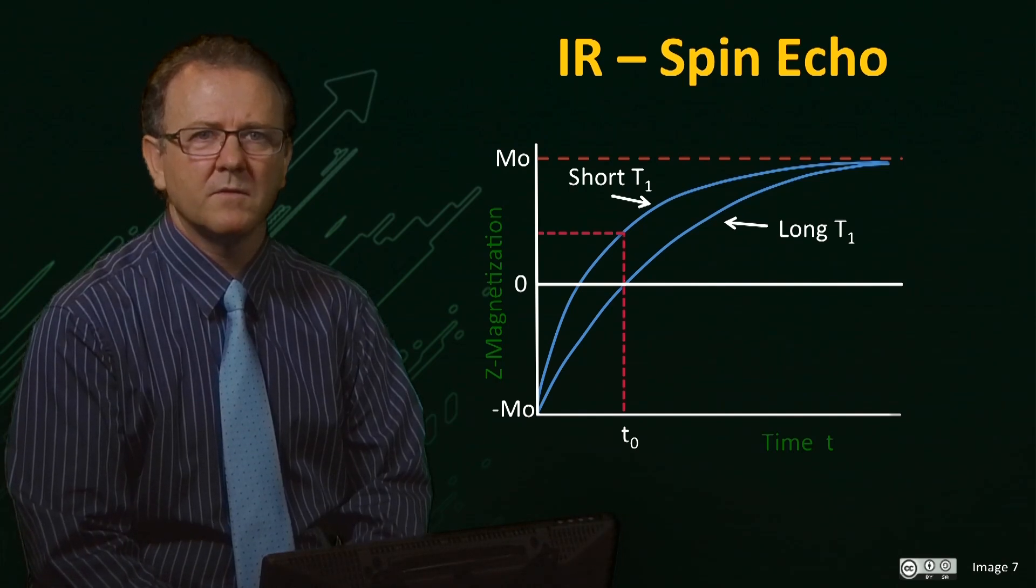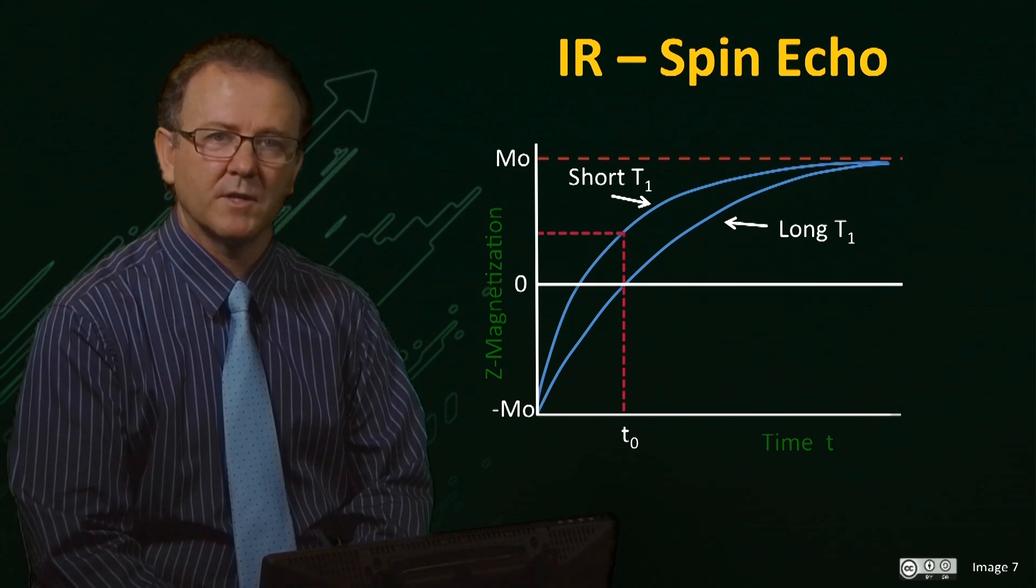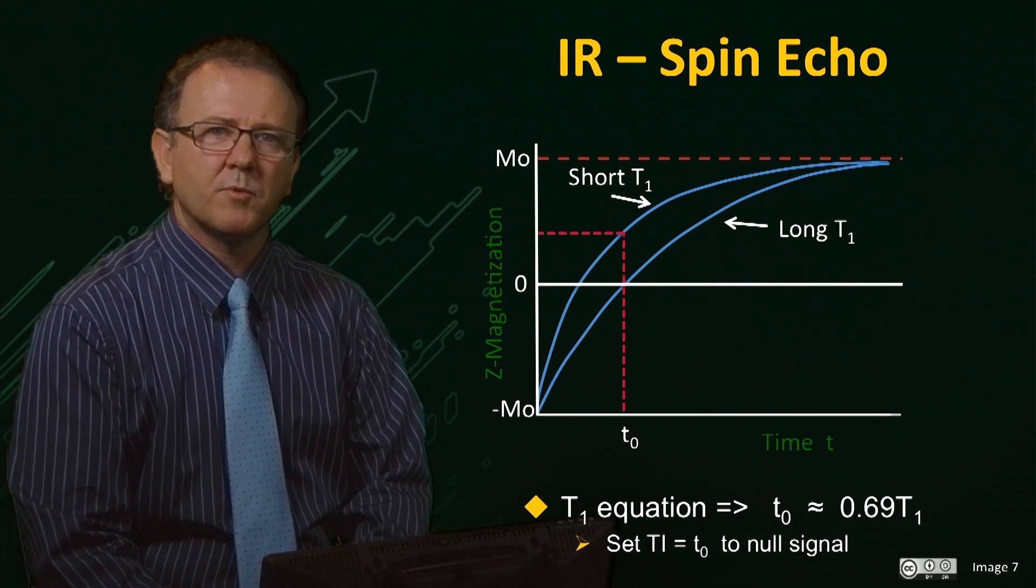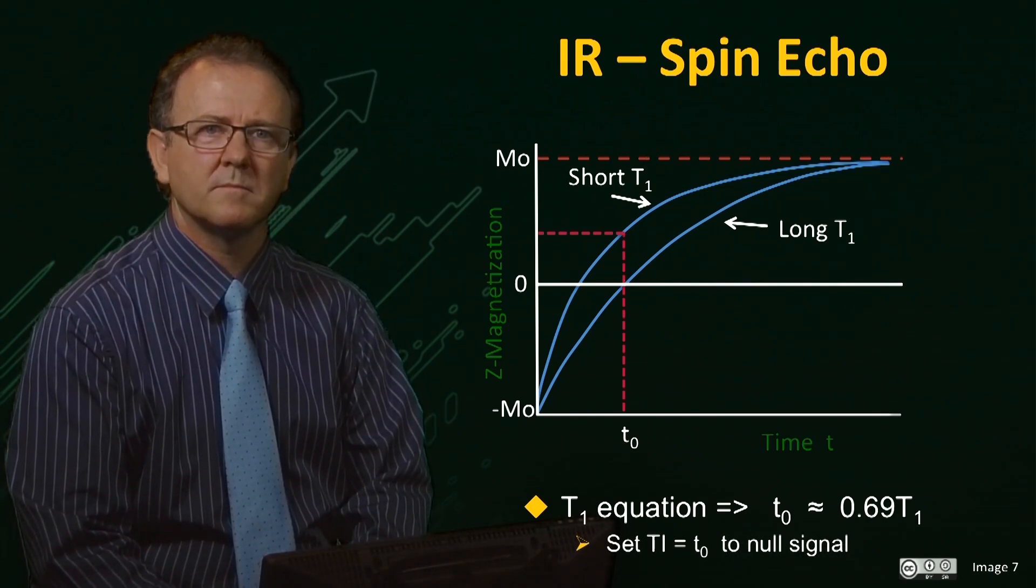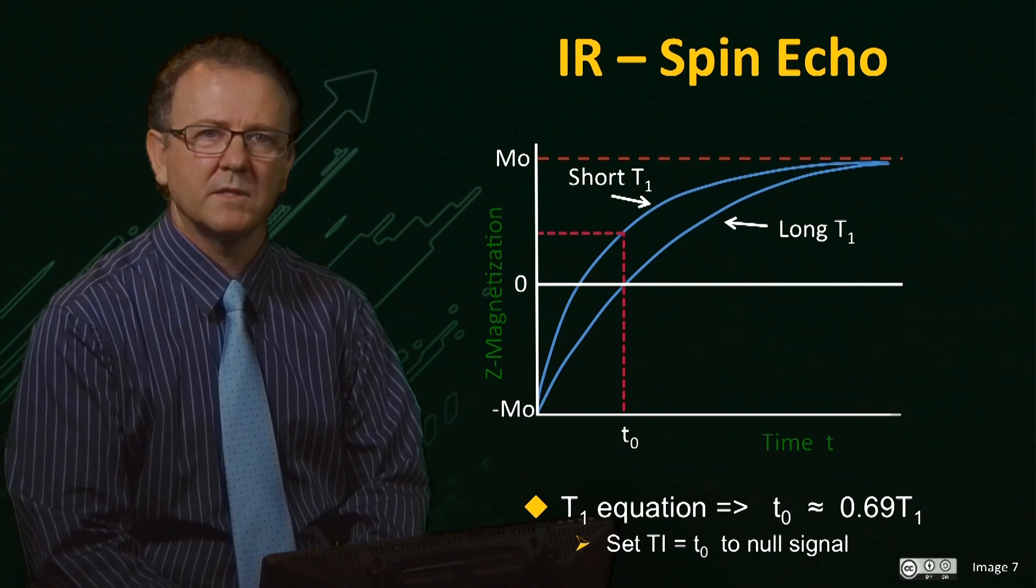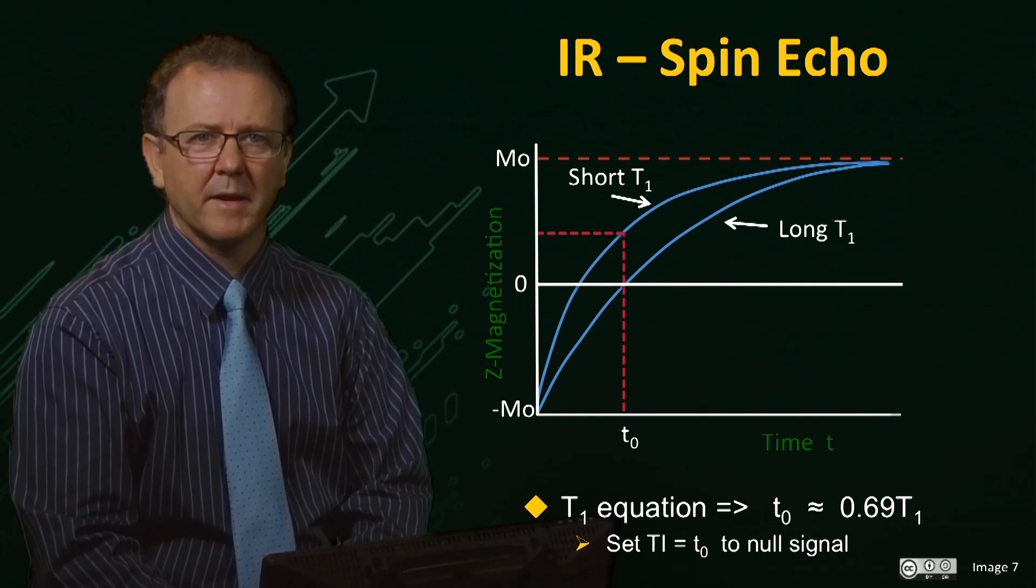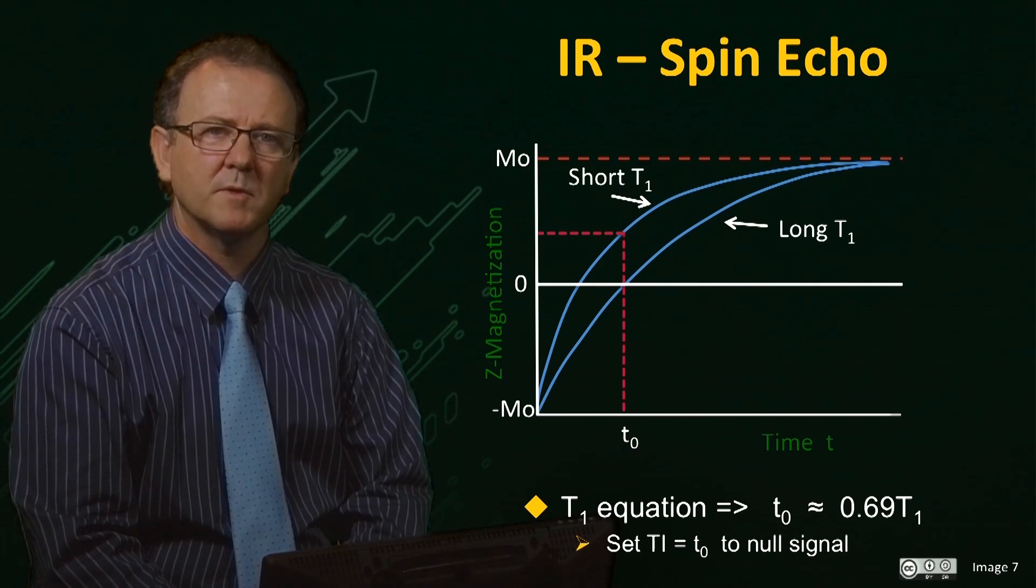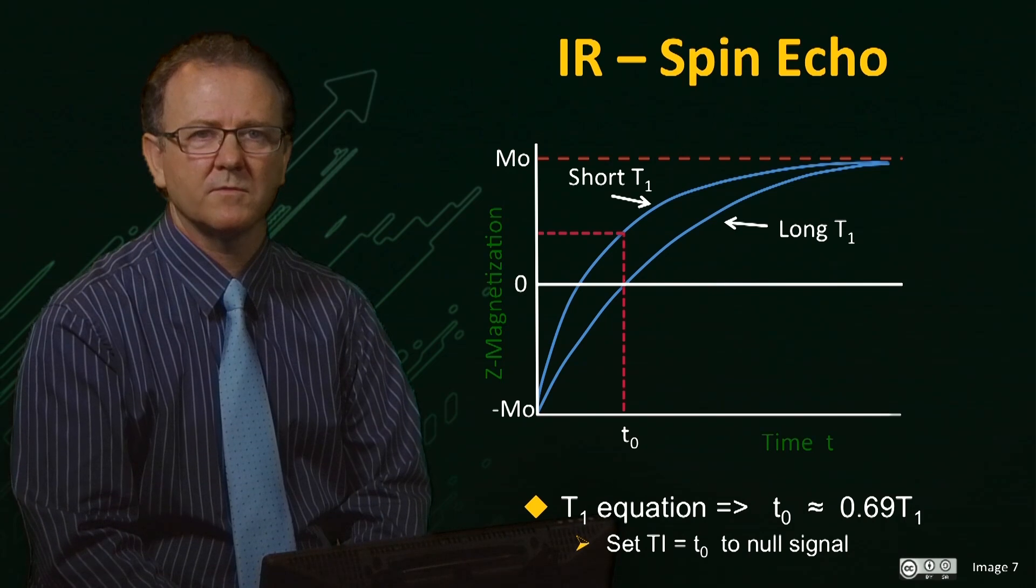In general, the equation that describes the relaxation of magnetization after an inversion pulse predicts that the null point T0 is approximately given by 0.69 times the T1, provided the magnetization is allowed to fully relax between the acquisitions. If the TR value is short so that the magnetization does not fully equilibrate between phase encoding increments, then the null time will be shorter and will depend on the value of TR.